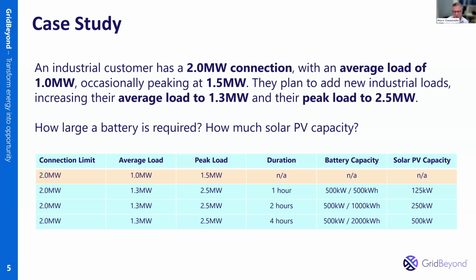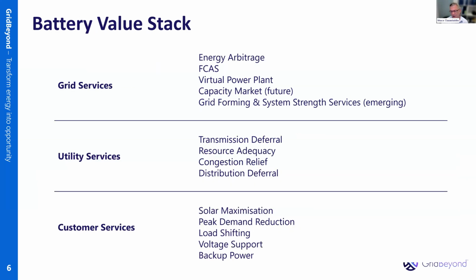So you've installed a battery, you've installed solar, and the whole idea behind it was, I want to avoid CapEx. But then you've got an asset that's sitting there, probably working a few times a year. What else can you get out of the battery? And this is where GridBeyond can add additional value. So when you look at the battery value stack, there's 3 areas that we break it down to. Grid services: this is the battery participating in arbitrage or energy, FCAS, capacity market, which is future, and grid forming and system strength services emerging. These can all be monetized. They've all got value, and the software that you use can unlock that value.